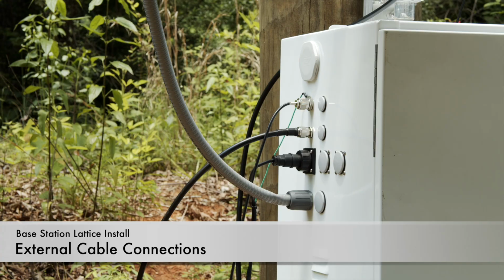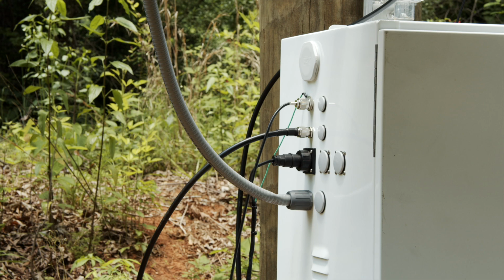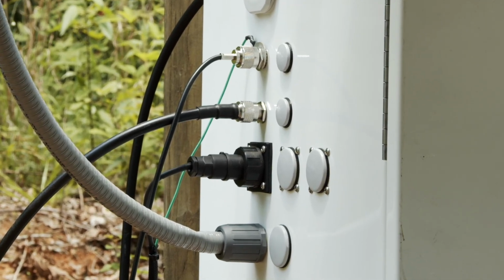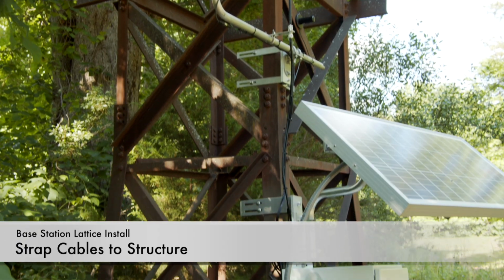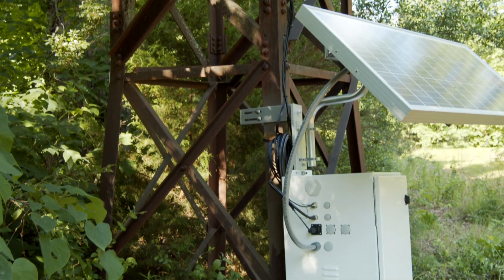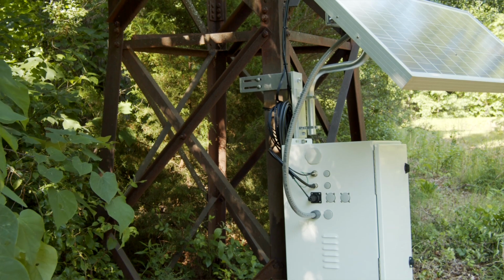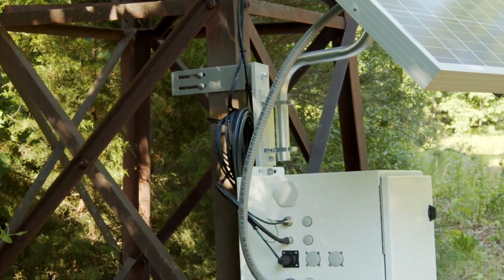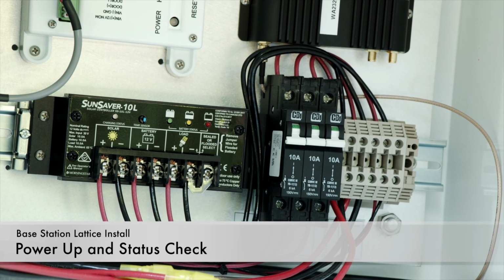External cable connections. Connect all the cables to the correct connectors on the side of the cabinet. Note the grounding lug of the weather transducer cable is connected to the connector for the cell antenna via a lock nut. The connections for the standard option include grounding cable, weather transducer cable, RF antenna cable, and cellular antenna cable. Strap cables to structure. Fasten the cables using tie wraps to prevent them from moving in the wind and being damaged by vibration. Power up and status check.